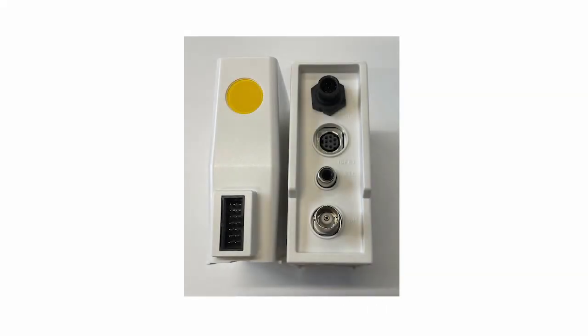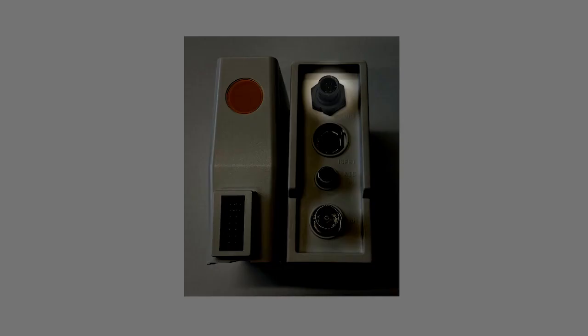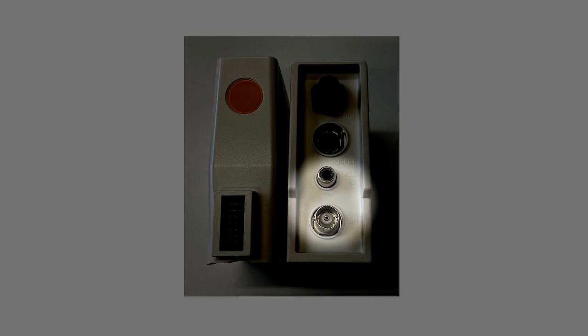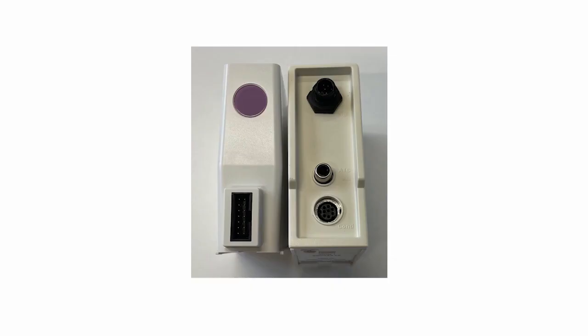The first module we see is the yellow module. This module is dedicated to measuring pH and redox. It has a mini LTW socket to connect the digital sensor. Below that, there's an input for the ISFET electrode. Then we also have a cinch socket for temperature probe and BNC socket for pH and redox electrodes with multi-pin or S7 cable.